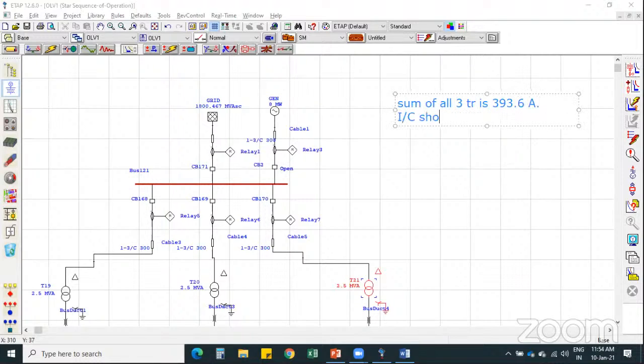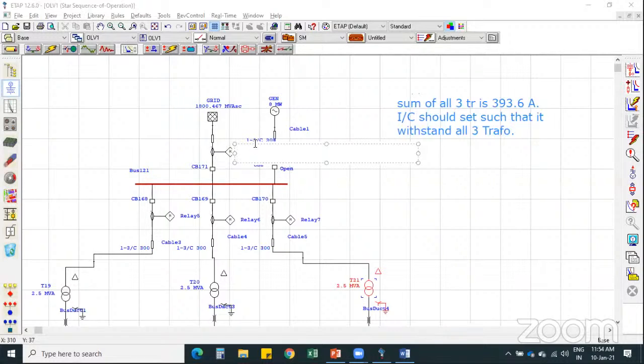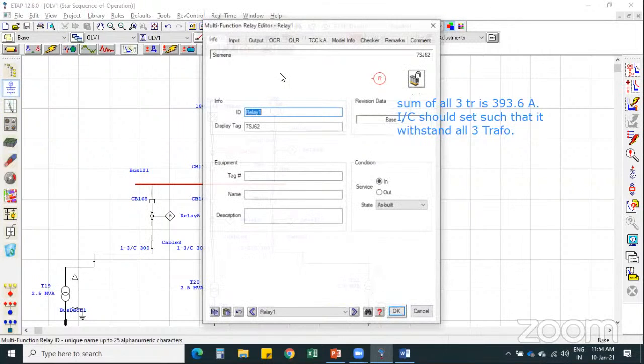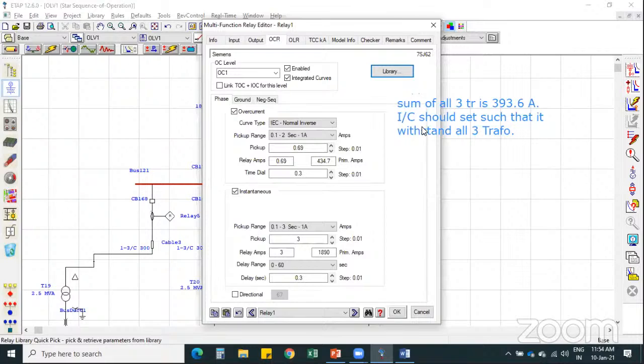So the incomer feeder should be set such that it withstands all three transformers. Here we will set this protection in such a way that there is a margin of 10 percent, because sometimes if two transformers are running at running load, it should withstand some overcurrent condition for certain time intervals. So we will set 393.6 with a 10 time margin, that is 432.96.